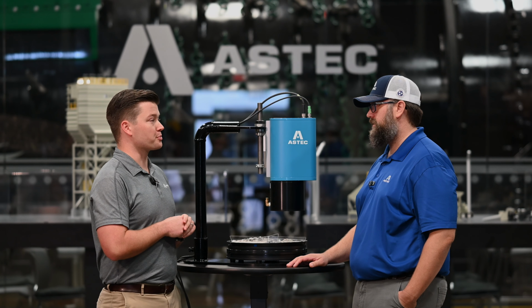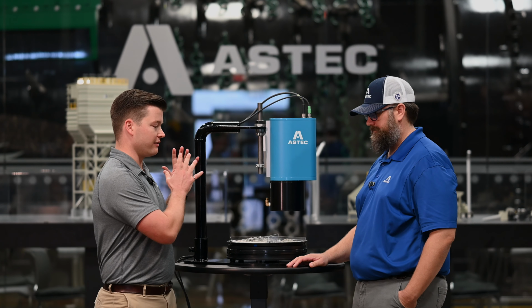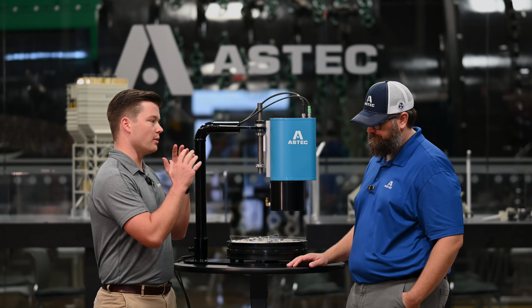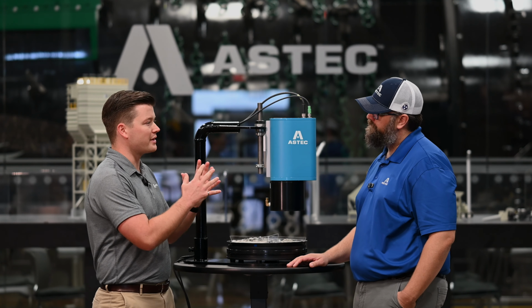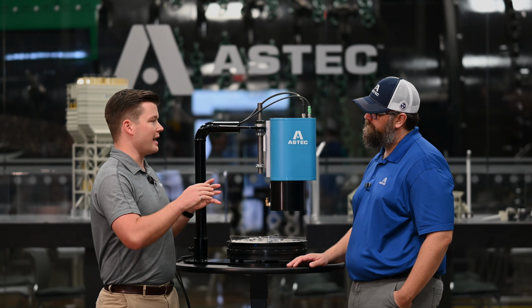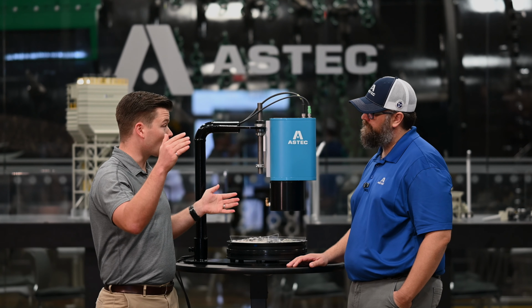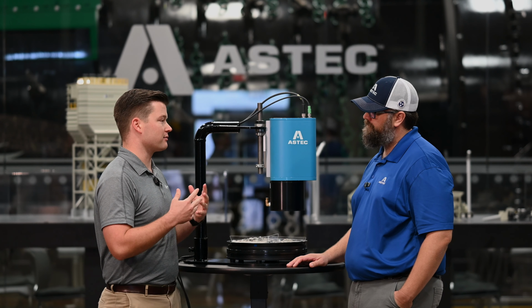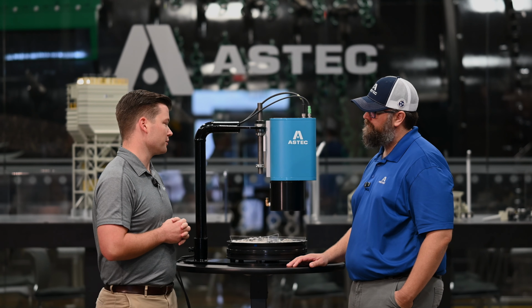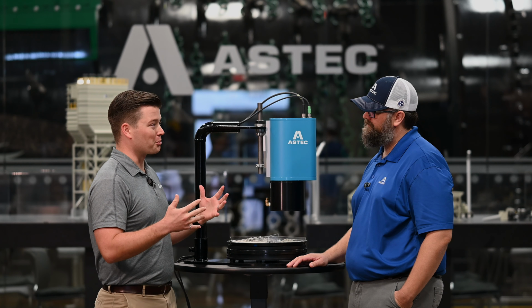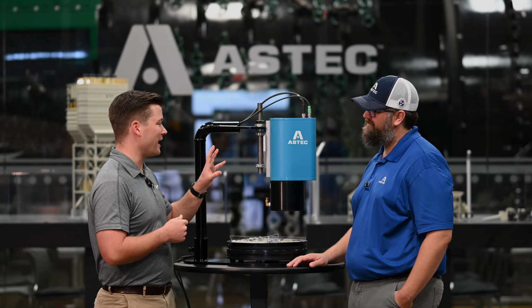However, these sensors perform best when you do 3: a very dry, a very wet, and then also a calibration around where that material normally is. That way you've got a nice calibration curve that the sensor is able to use whenever it sees other moisture values coming through.